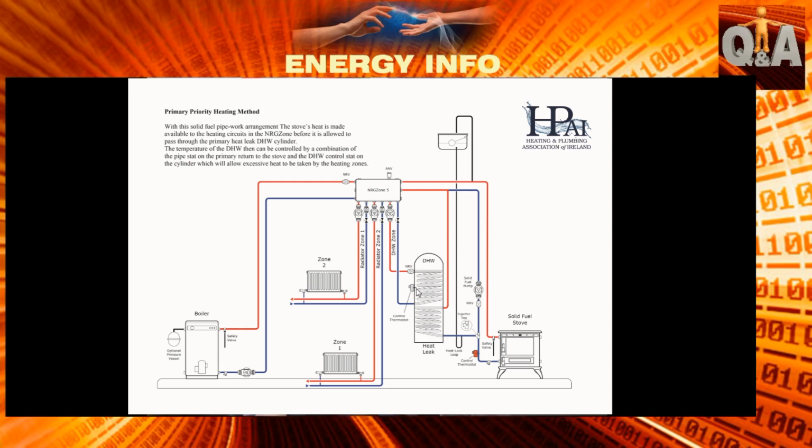What does that stat then actually fire? What does that trigger? The boiler stat brings on the boiler pump, whereas the other cylinder stat could prevent radiator zones from coming on. In a motorised valve system that would be called a W plan. An S plan is where you'd have the two motorised valves. The Y plan is where you'd have a Y shape or a T shape valve, but a W plan is where you'd have the hot water satisfied before the zones come on.